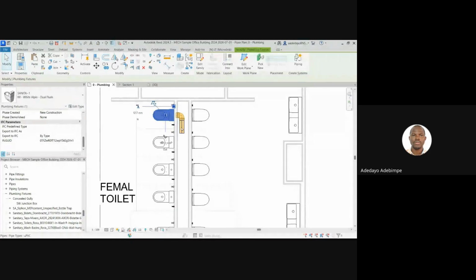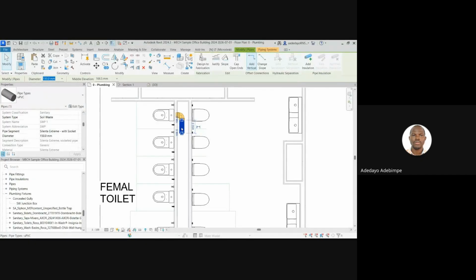Now, this pipe, usually, the way I like to design is maybe because of my experience. I've been a contractor. I've supervised installation of things like this. You will have your pipe at low level. I don't know if you get that. Our pipe will be at low level in the wall, in the shaft, but they've graciously provided us with a shaft to use.